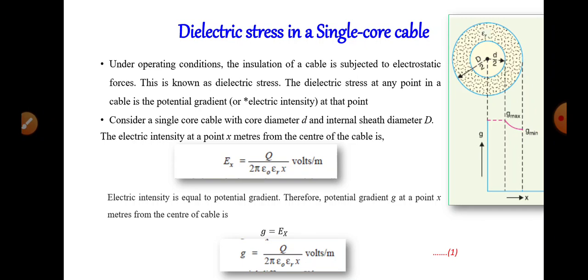Consider this figure having conductor diameter d (small) and internal sheath diameter D (capital). The electric field intensity at a point x from the center of the cable will be: E_x = q / (2π·ε₀·εᵣ·x) volts per meter. This is also the potential gradient, so electric field intensity equals potential gradient. Therefore, potential gradient G = q / (2π·ε₀·εᵣ·x) volts per meter.